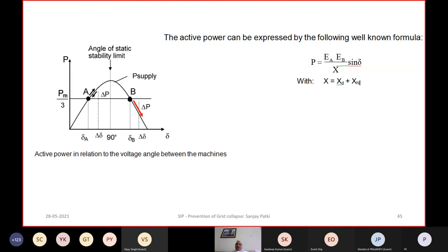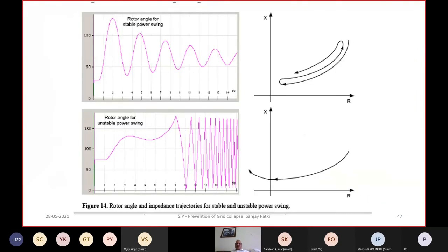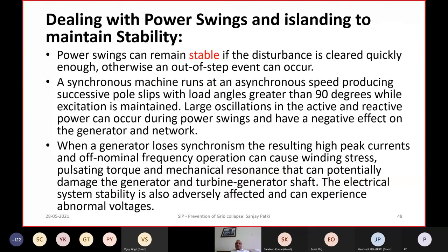That means by way of transfer trip or other communication based scheme, we must ensure that almost all faults are cleared by high speed primary protection, at the most cleared by backup protection, which is your LBBU protection, that is 200 milliseconds. So this is what the overall scheme will ensure.